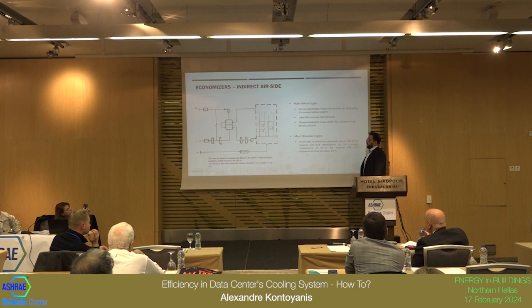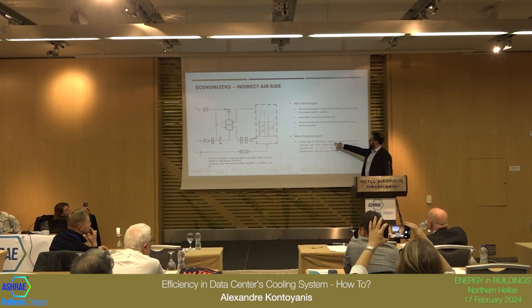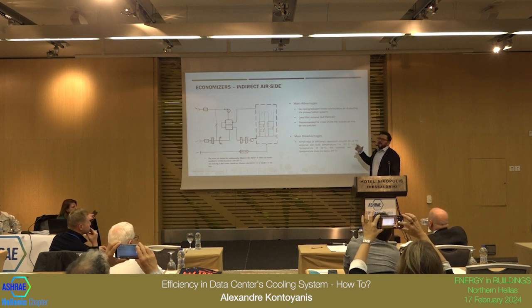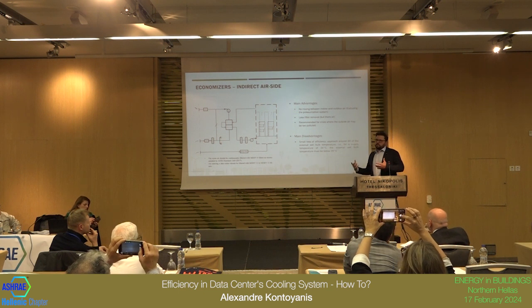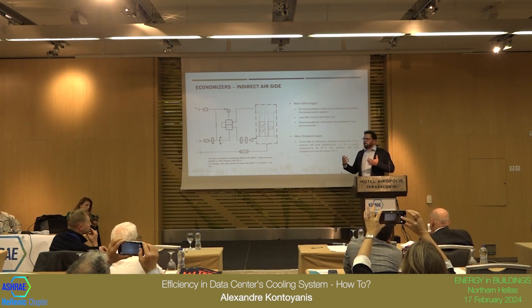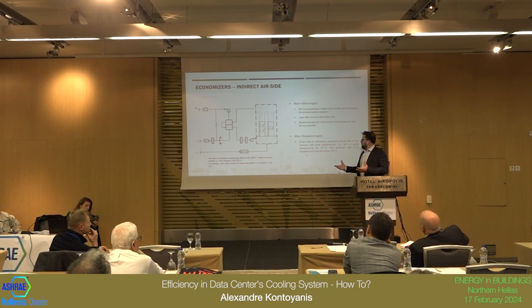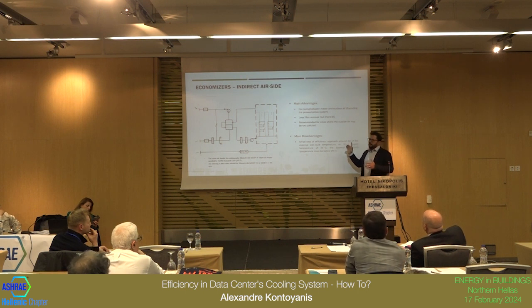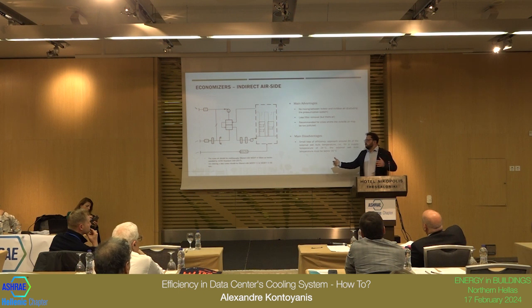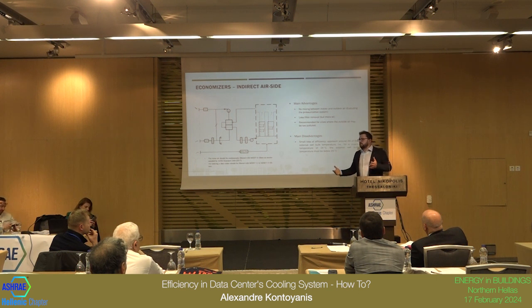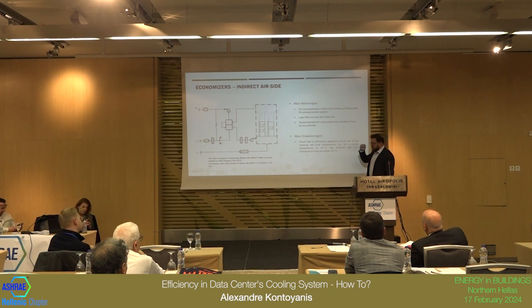But of course, you have disadvantages. We lose a little efficiency. Now, the approach can be around 4K to 8K. It depends on the machine you're buying. This is almost directly proportional to the size of the heat exchanger. So if you want a very efficient heat exchanger, it goes big. It's expensive. Sometimes you don't have the space to do this. So it goes from 4 to 8. Most efficient is 4.